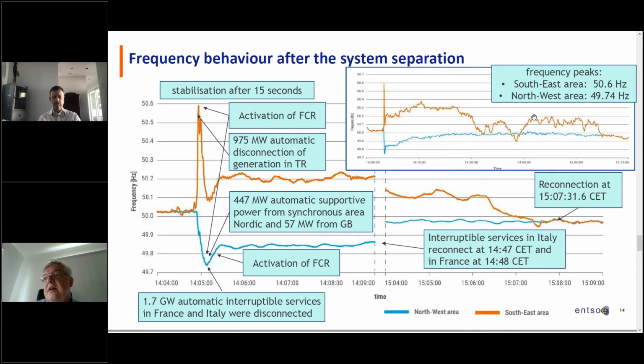If this oscillation had lasted, instead of a few seconds, 10, 20, 30 seconds, we might have lost the whole of the Balkan area, and then a lot of generation and loads in the rest of Europe as well. So it could have been much worse, but luckily these distance protections managed to split the system very quickly, and the system stabilized very quickly after the interruption.